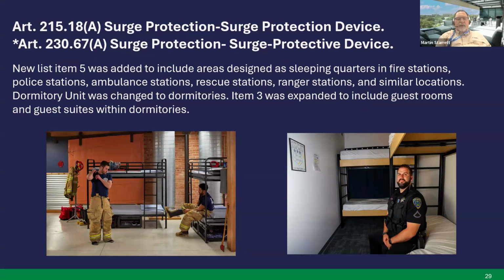Okay, so a couple of articles with similar language. Article 215.18(A) and Article 230.67(A), which is found in the service article. Surge protection devices. A new list item 5 was added to include areas designed as sleeping quarters in fire stations, police stations, ambulance stations, rescue stations, ranger stations, and similar locations. Dormitory unit was changed to dormitories, and then item 3 was expanded to include guest rooms and guest suites within dormitories. So they've kind of expanded the bedroom requirements and called out these particular types of locations. I'm sorry, I can't think of the word, but they expanded it.